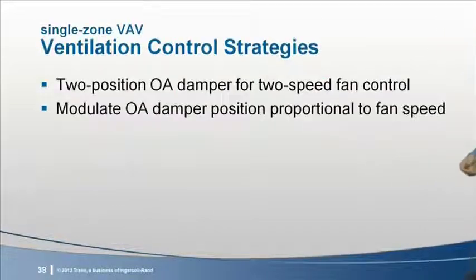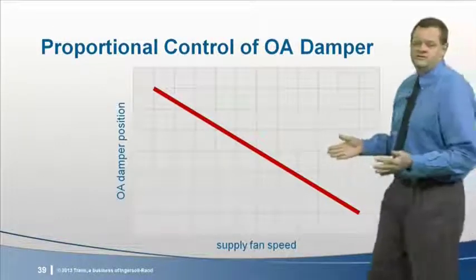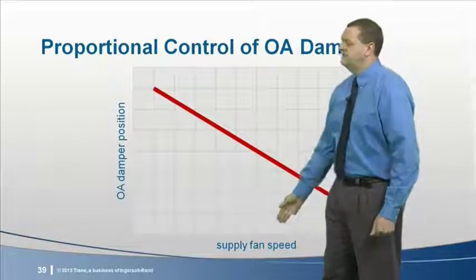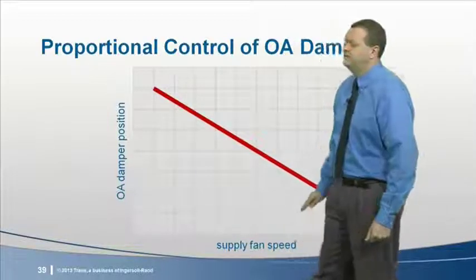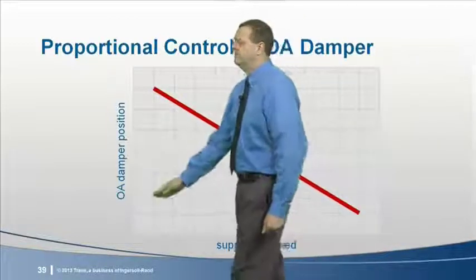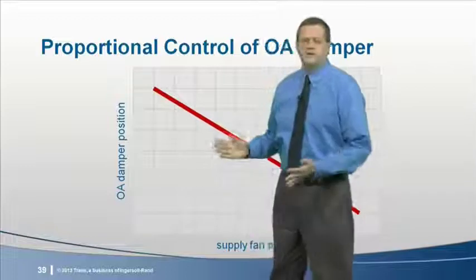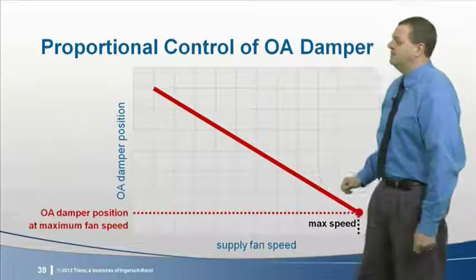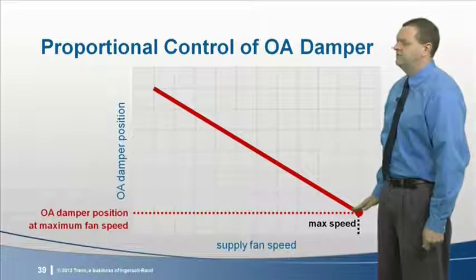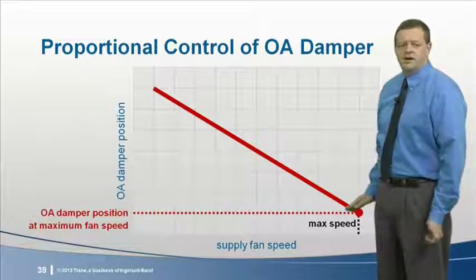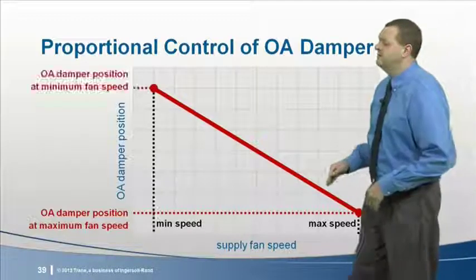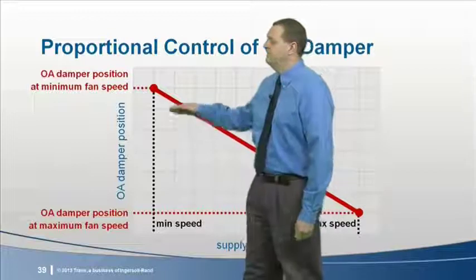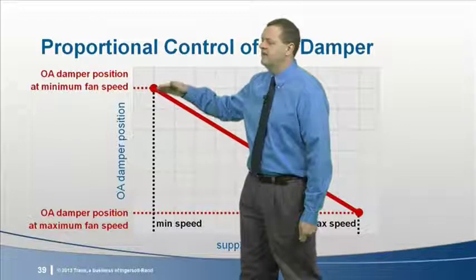Next, for systems that use a variable speed fan, a relatively inexpensive solution could be to modulate the position of the outdoor air damper in proportion to the changing fan speed. I'll demonstrate this with this chart. Supply fan speed is on the x-axis from minimum speed to maximum speed, and damper position is on the y-axis from fully closed to fully open up here. First, with the system operating at the design supply airflow and maximum fan speed, the outdoor damper is positioned to a set point that brings in the quantity of outdoor air required by code. Then, when the system is operating at minimum airflow, the damper is adjusted to this more open position in order to bring in the same CFM of outdoor air.